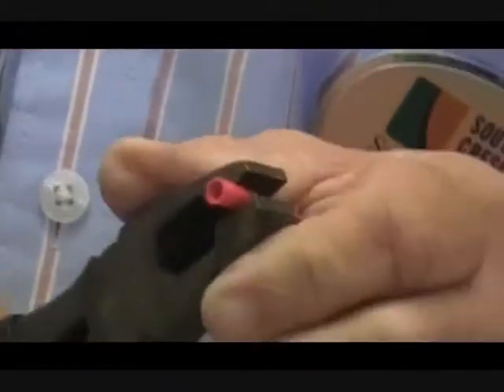Now, I've seen folks use a pair of pliers more than one time. And I'm going to try to demonstrate what happens when you do that. If I take a pair of pliers instead of the proper tool and I crimp it, it's going to look like I've done a good job. Mashed it flat, only one problem. I don't know if you can see this or not, but that's actually loose in there. Whereas this one, it's not going to come loose. Loose connections cause problems. That's all it is to it. I've seen loose connections cause thousands of dollars of damage.